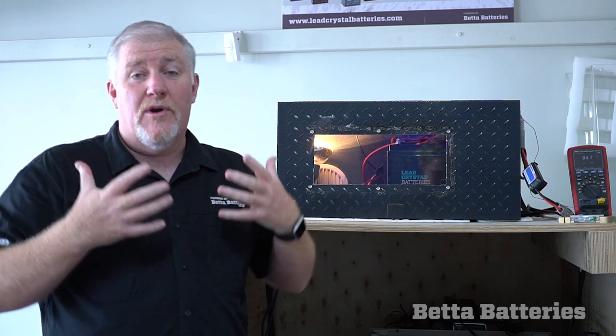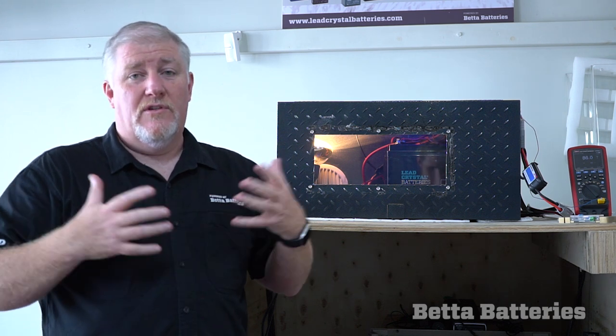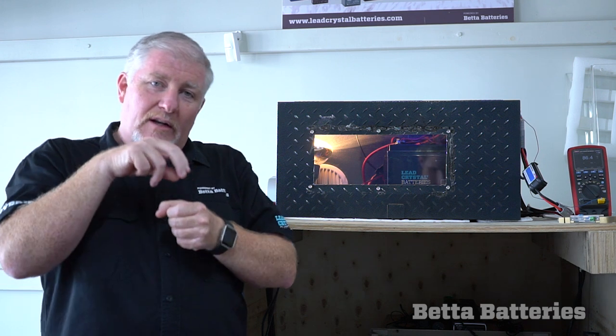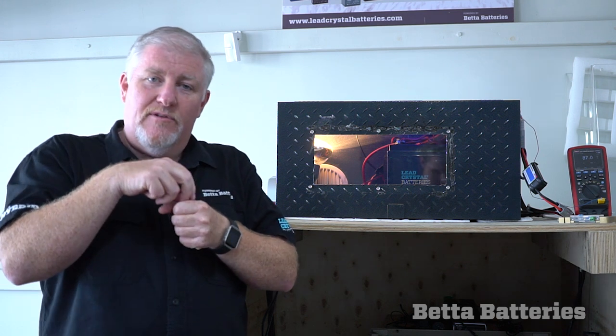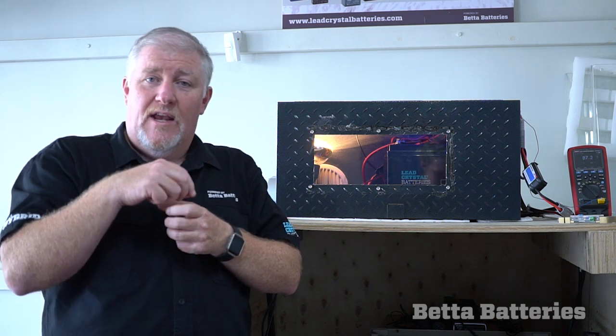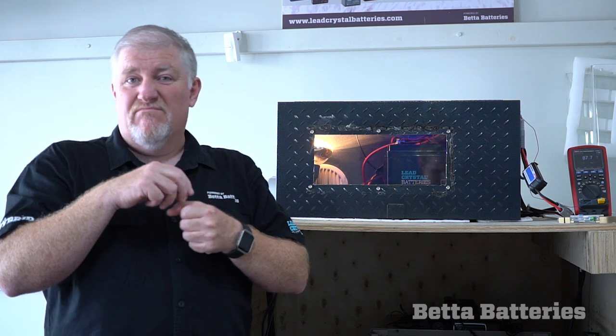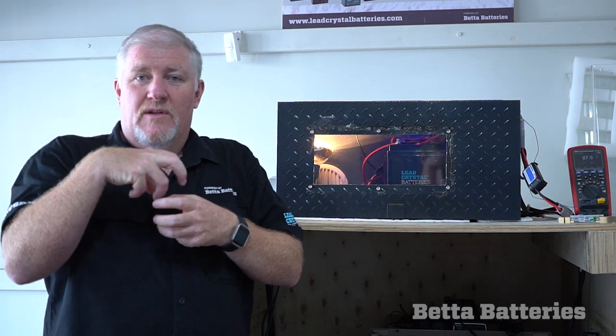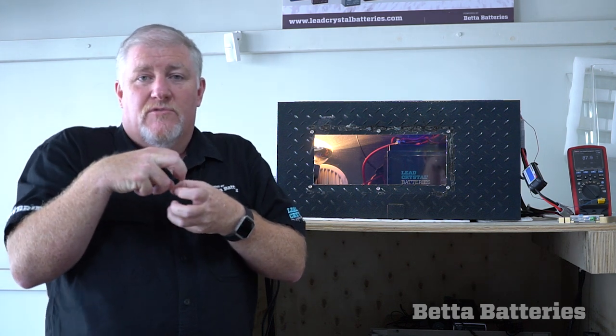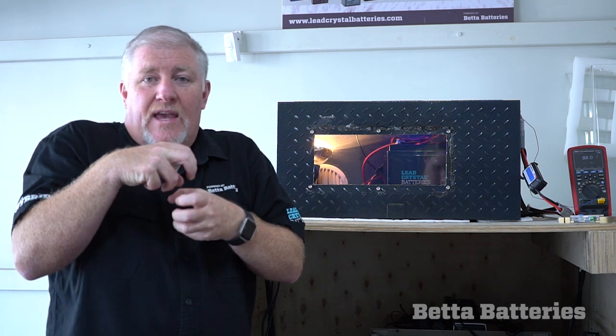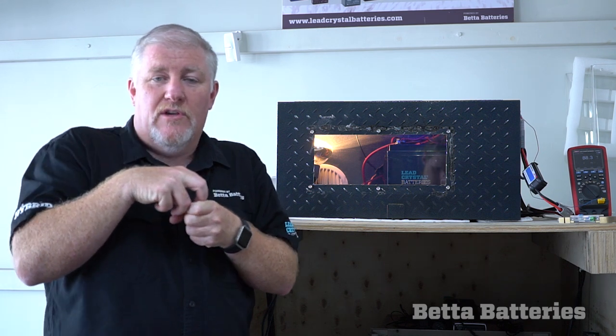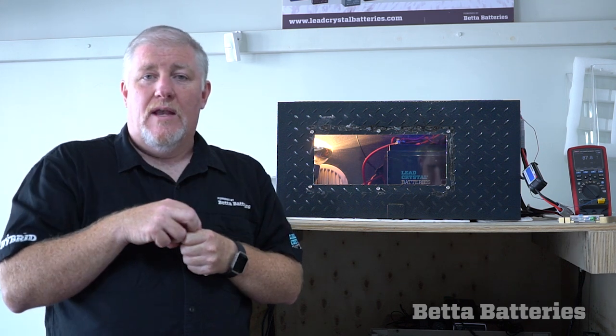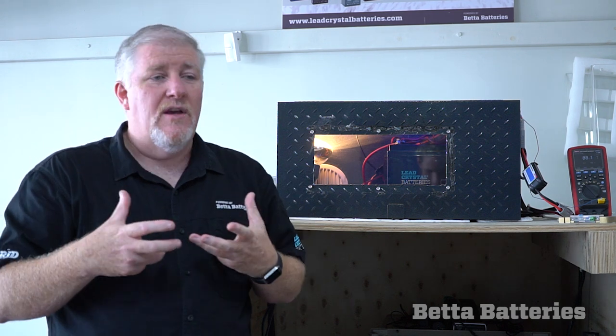It's just literally the pressure inside that battery is so great. So what happens is the little rubber caps that are meant to release the vent above about that 70 degree mark, the rubber and the plastic becomes tacky and the caps grab onto each other so they don't release and therefore the pressure builds up inside the battery.